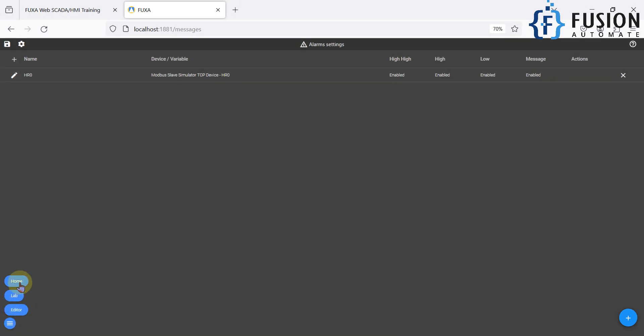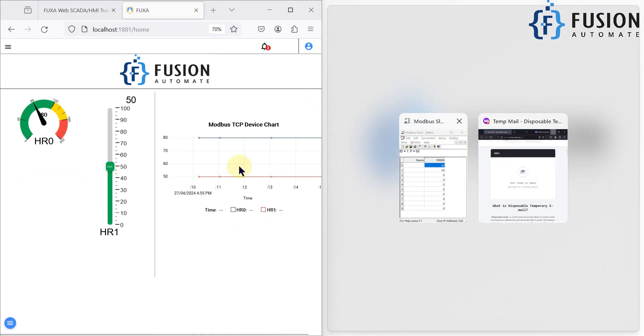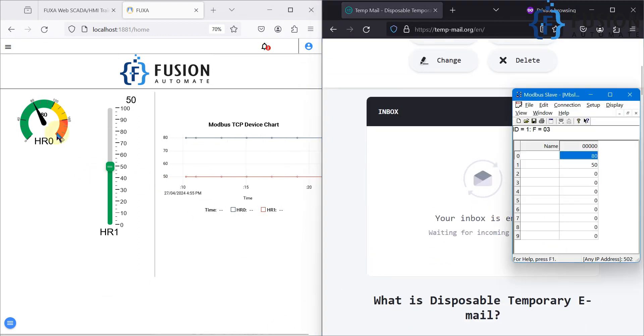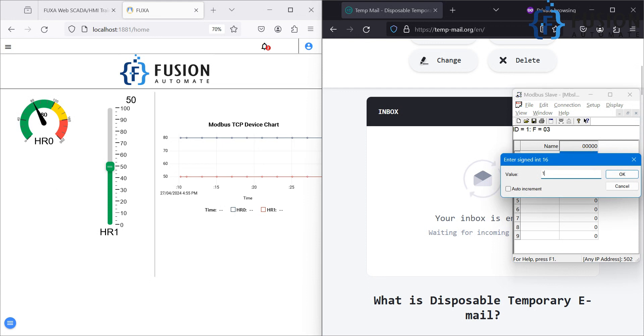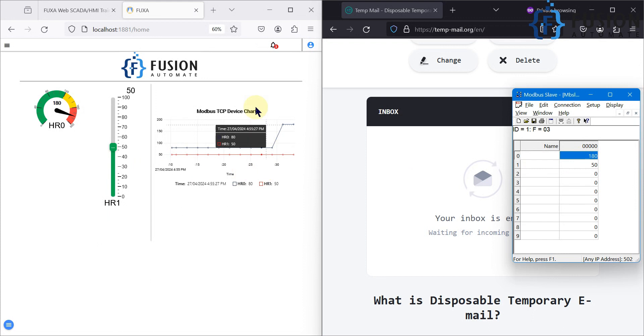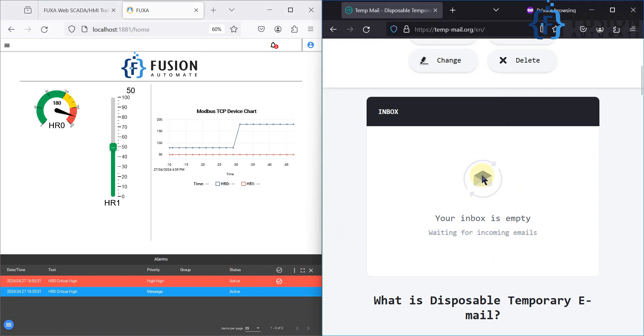Now we can go to the home dashboard. I'm going to open the FUXA SCADA dashboard and the temporary mail side by side. I will change the value of holding register 0 to 180, which falls under the high-high alarm range. You can see the graph value is 180, and the alarm shows HR0 critical high, with priority high-high and status active. We will not acknowledge it — we'll wait for the email first.